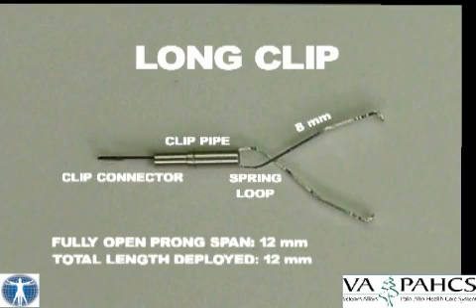This is a close-up view of the long clip with right angle prong tip. The clip connector will attach to the hook on the clip fixing device. The spring loop will be retracted after the clip is exposed prior to deploying to fully open the clip prongs. When fully open, the span between the prongs is 12 millimeters for the long clip. Once deployed, the length of the long clip is 12 millimeters also. For the standard clip, the clip prong span is 6 to 7 millimeters and the deployed length is 1 centimeter.